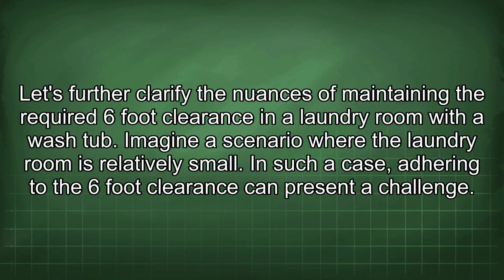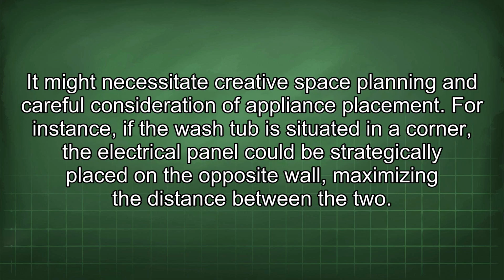Let's further clarify the nuances of maintaining the required 6-foot clearance in a laundry room with a wash tub. Imagine a scenario where the laundry room is relatively small. In such a case, adhering to the 6-foot clearance can present a challenge. It might necessitate creative space planning and careful consideration of appliance placement. For instance, if the wash tub is situated in a corner, the electrical panel could be strategically placed on the opposite wall, maximizing the distance between the two.